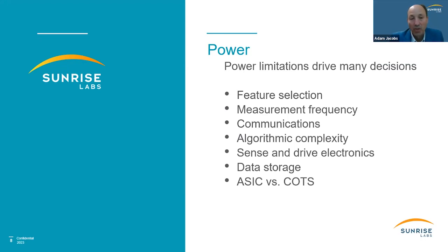One factor is just what features you choose to put in your device—some can be quite power hungry, depending somewhat on measurement frequency. If you're taking a temperature measurement once an hour or twice a day, it really doesn't take any power at all, but if you're looking at an ECG or EEG continuously, that can take a lot of power. The more you put into the device, and the more continuous the measurement, the more power it takes. So those are things to look at carefully to figure out what you really need for clinical efficacy.